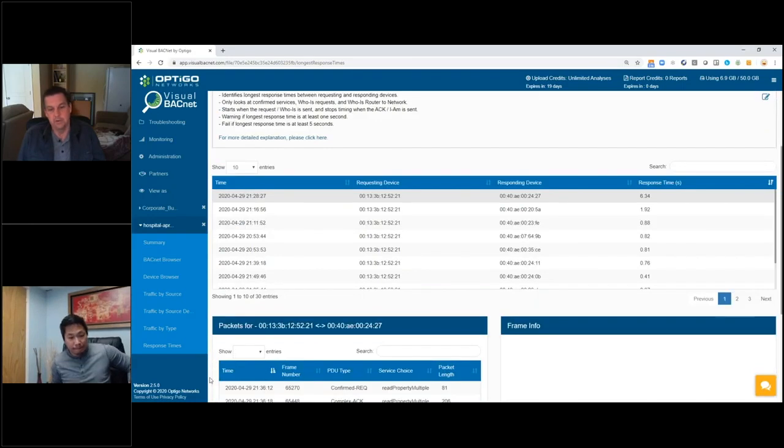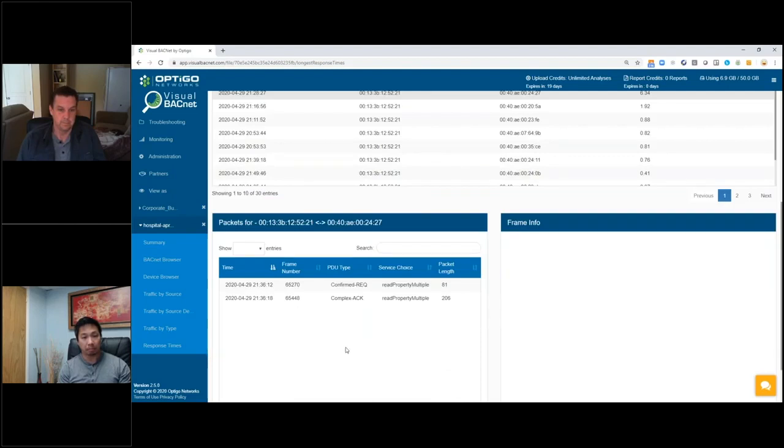As a quick note, inside of all BMS programming, if you set a data request from one device to another, we can always time it. So if you suspect your system is slow, set a source and an end destination, and we can simply time it and see how long it takes for data to get through your network. I know when customers say my graphics are slow, that is a very, very vague problem, and it takes a while to go search, but this is a good way to see it.